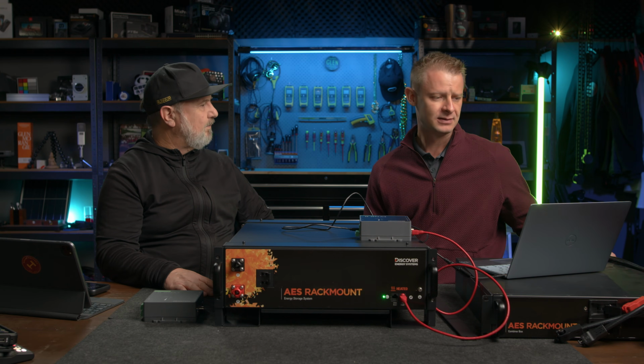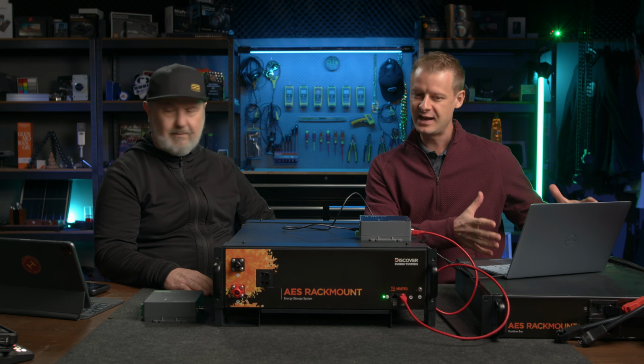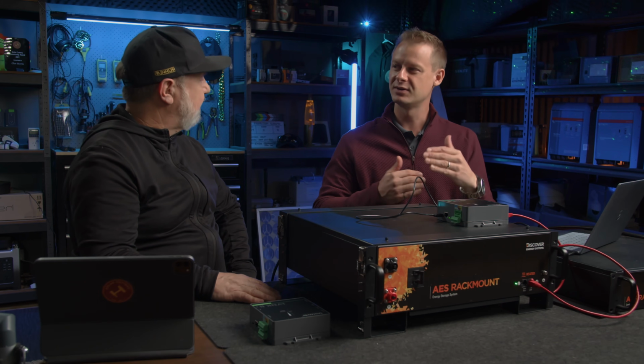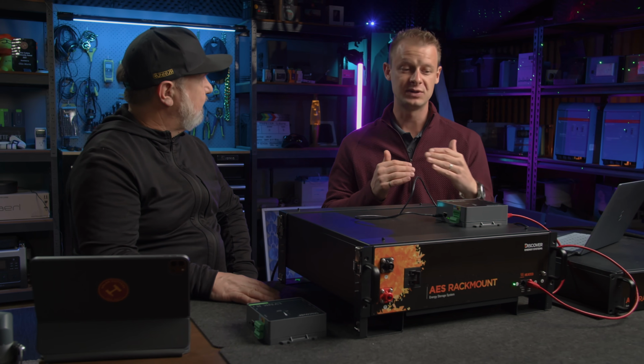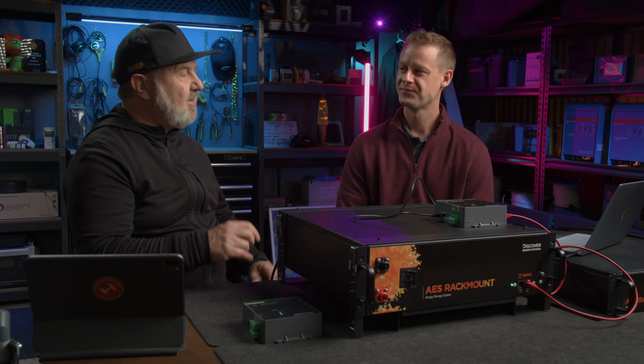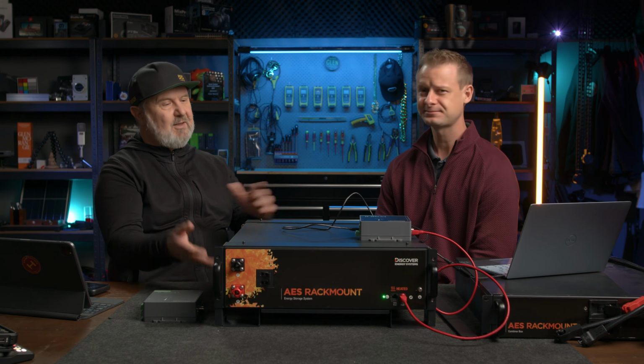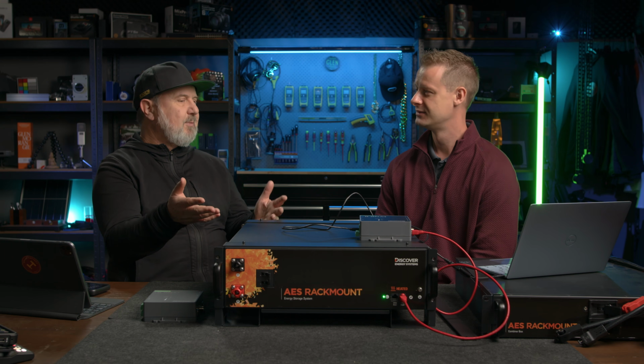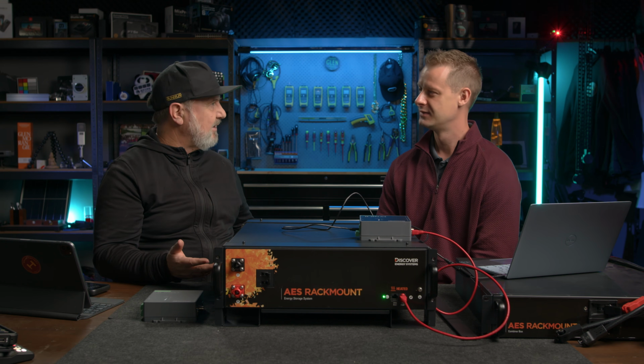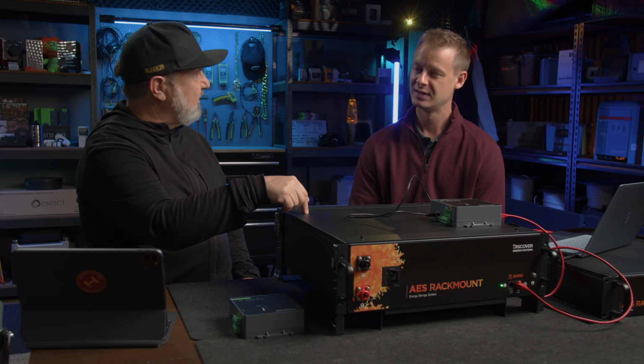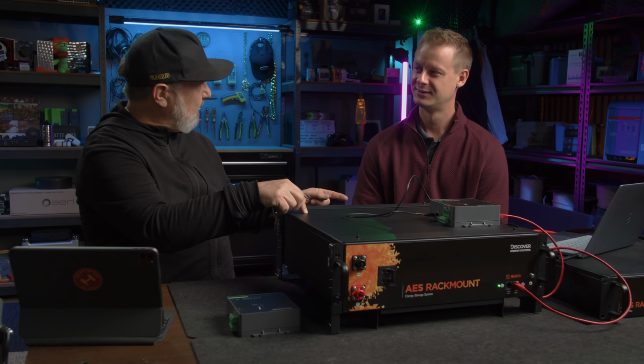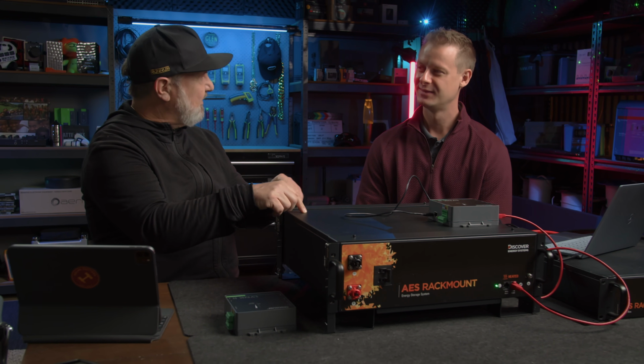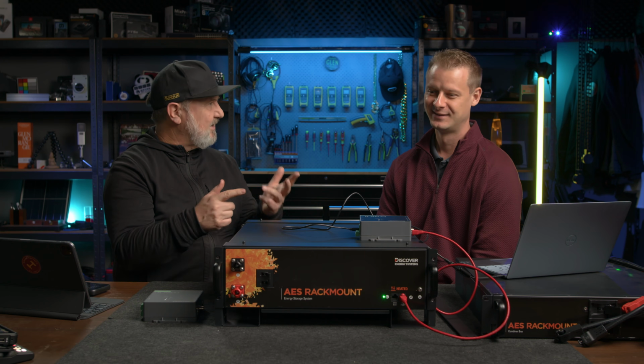So by having a lengthy cable, it acts as a dampener, encouraging the batteries to more equally share the current of the system. You might think just because they're all connected to a common DC bus, they'll all charge and discharge at the same rate. But when you've got slight impedance differences inside the cells, unless you have that dampening, it gets magnified - so some batteries get more and others get less.